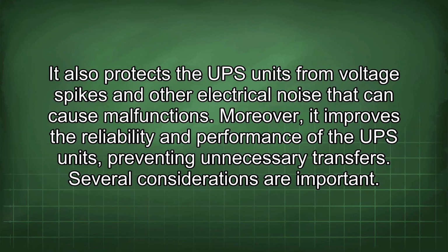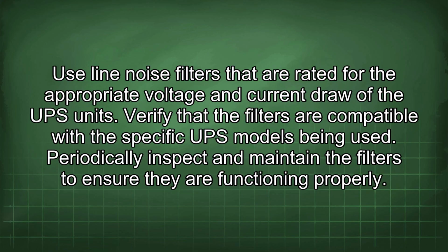Several considerations are important. Use line noise filters that are rated for the appropriate voltage and current draw of the UPS units. Verify that the filters are compatible with the specific UPS models being used. Periodically inspect and maintain the filters to ensure they are functioning properly.